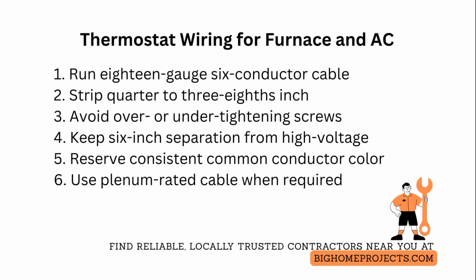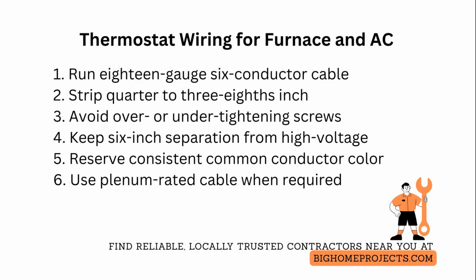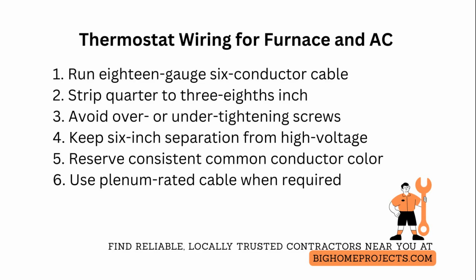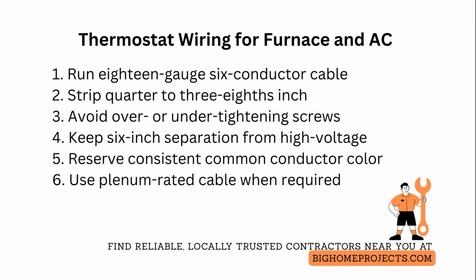For long runs over 100 feet, prefer 18 gauge over 20 gauge to reduce voltage drop. If you must exceed 150 feet, consider thicker 16 gauge for critical signals. Label both ends with heat, cool, fan, common, and accessory names to speed troubleshooting and future upgrades, and install a small service loop near the equipment to relieve strain.